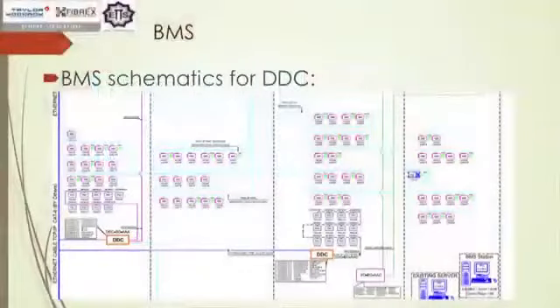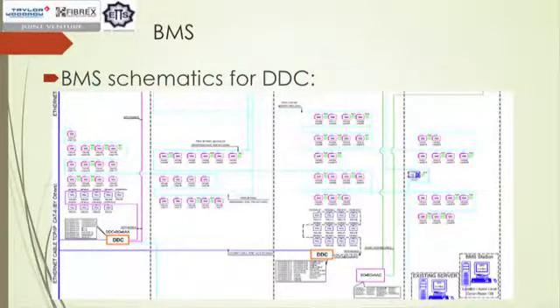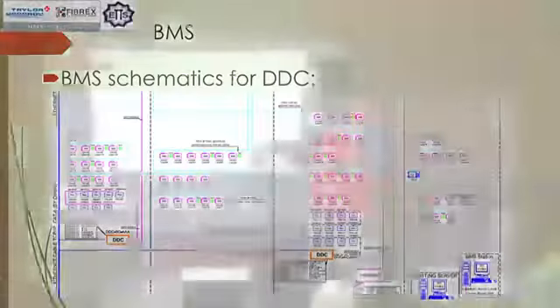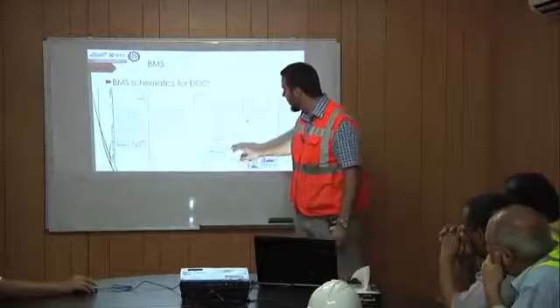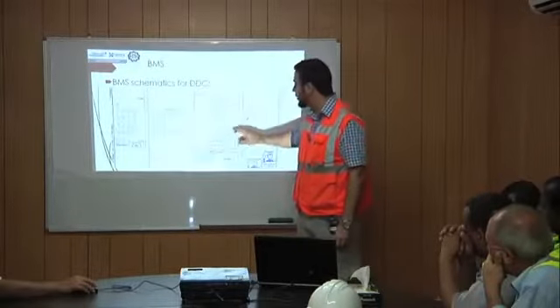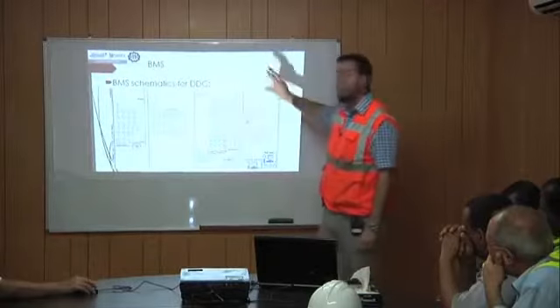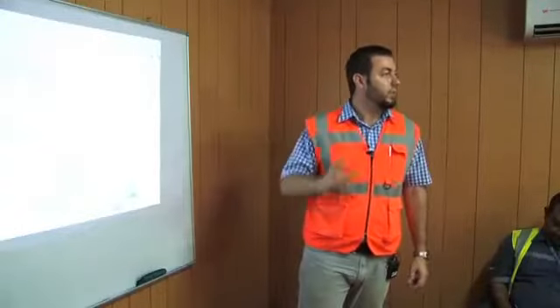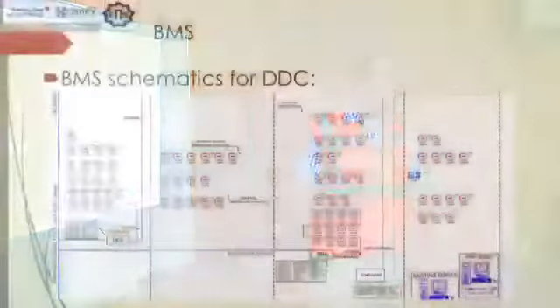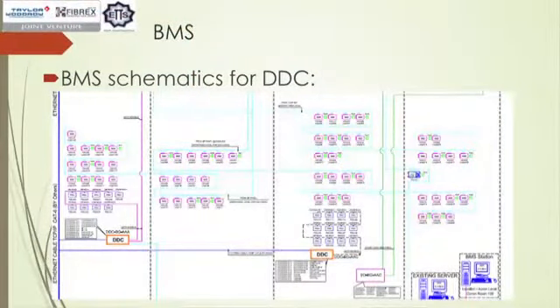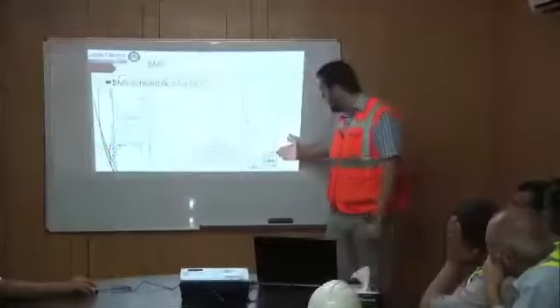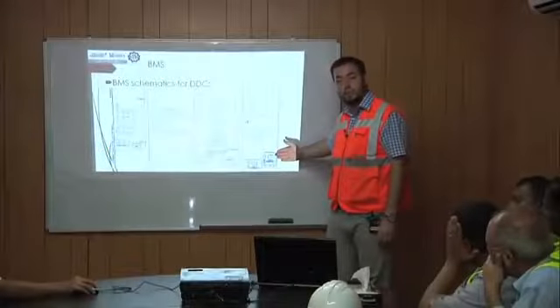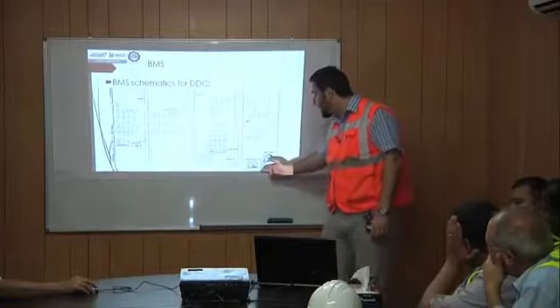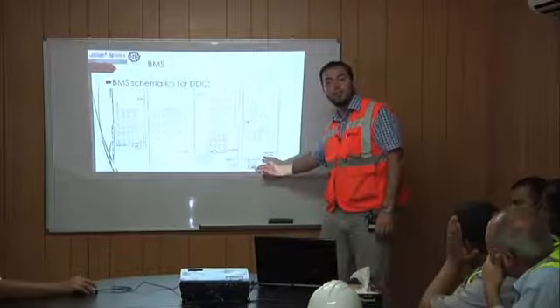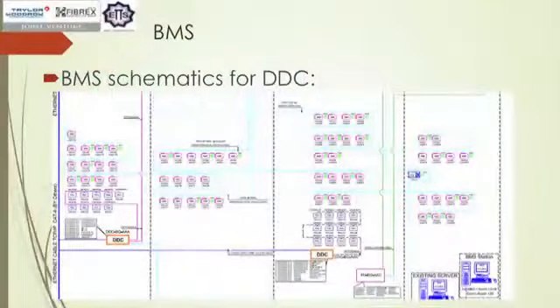Okay, so I took a small screenshot of the DDC panels. We've got 1, 2, and it kind of shows the interconnection, and each DDC panel, what is it affecting or what is it controlling and what is it monitoring. The specifics are there in the operation manual. It's going to be a hassle going into it. And we've got the BMS station that is located in the UPS room right now, and it's directly integrated and it's connected to the main existing Terminal 3.